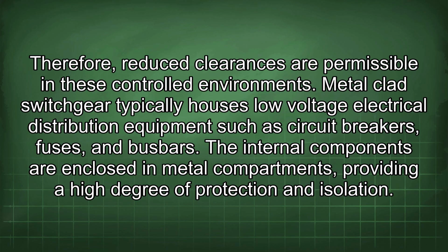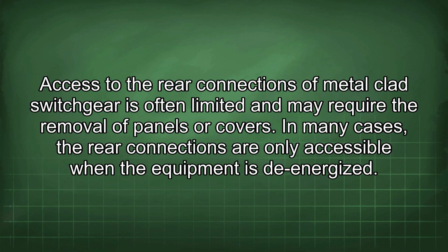Metal-clad switchgear typically houses low-voltage electrical distribution equipment such as circuit breakers, fuses, and bus bars. The internal components are enclosed in metal compartments, providing a high degree of protection and isolation. Access to the rear connections of metal-clad switchgear is often limited and may require the removal of panels or covers. In many cases, the rear connections are only accessible when the equipment is de-energized.